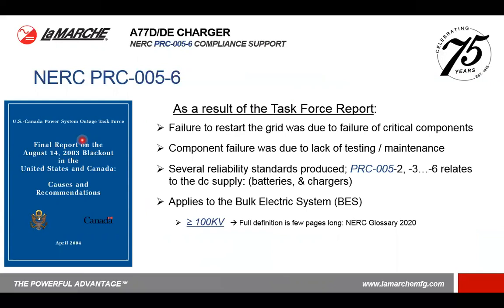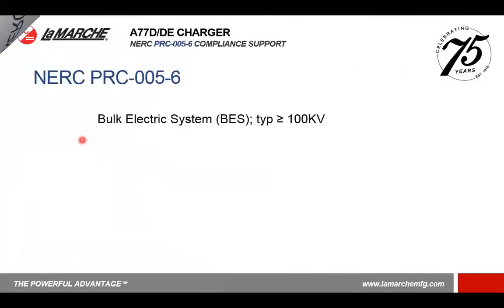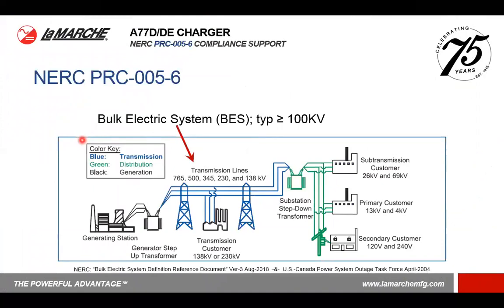PRC-005-2 was the first of them to link the DC supply, including batteries and chargers. Since then, PRC-005-2 has been replaced by -3, -4, -5, and ultimately -6. These standards apply to not all stations, but they do apply to systems that are on the bulk electric system. You can view a several-page definition within the NERC glossary, but essentially it comes out to greater than 100 kilovolts of transmission.